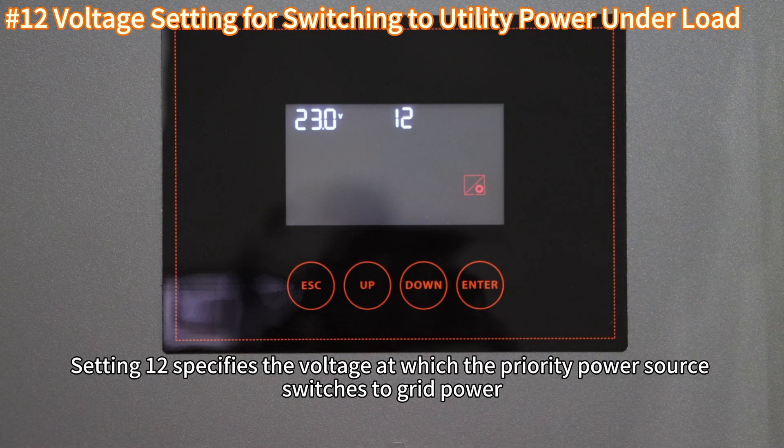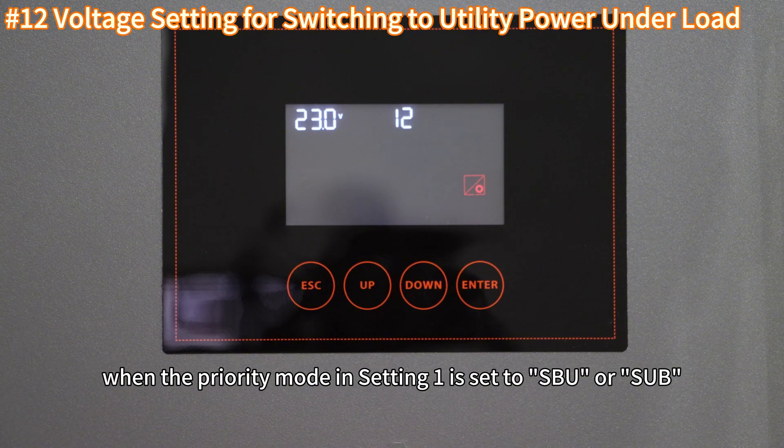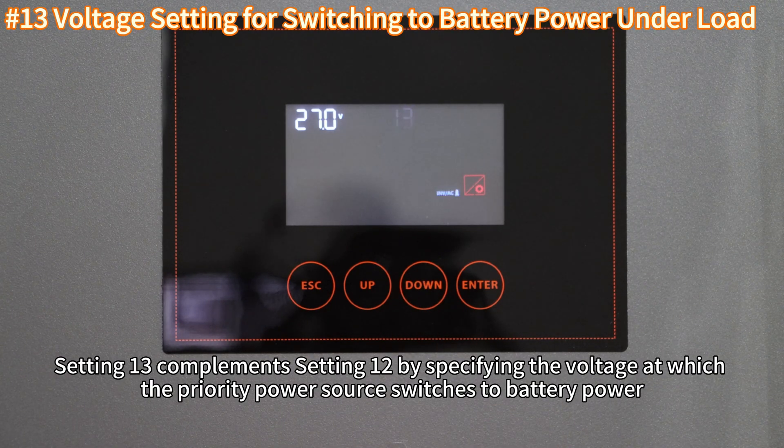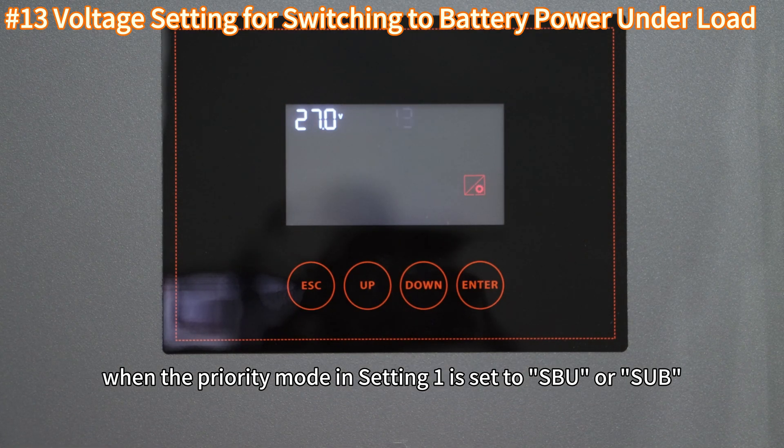Setting 12 specifies the voltage at which the priority power source switches to grid power when the priority mode in Setting 1 is set to SBU or SUB. Setting 13 complements Setting 12 by specifying the voltage at which the priority power source switches to battery power when the priority mode in Setting 1 is set to SBU or SUB.